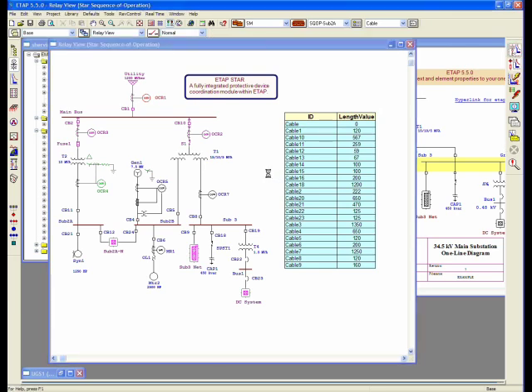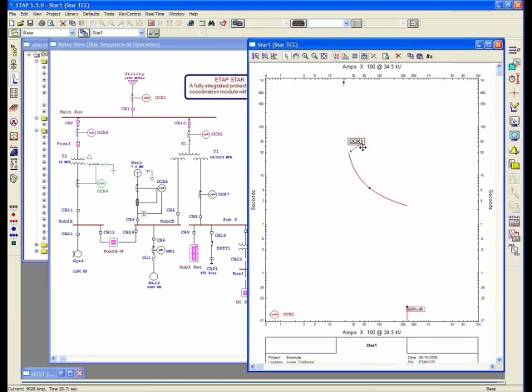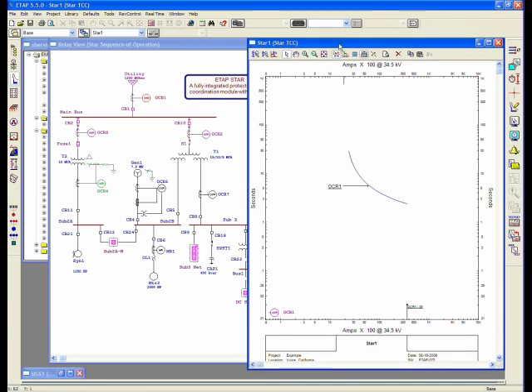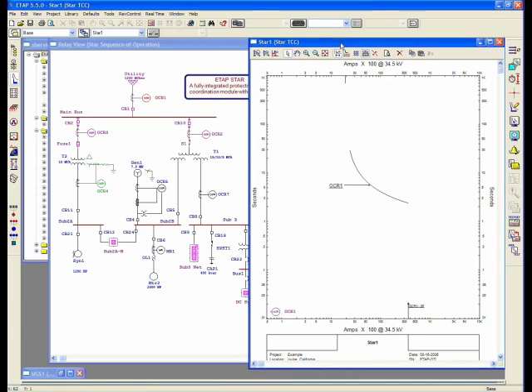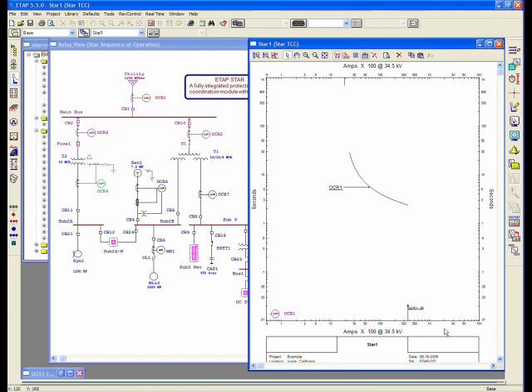What the program does, it brings that one-line element onto a TCC view and shows the label of the device, OCR1, and shows the curve for that device. This is created in what we call the star view, which is essentially a time-current characteristic curve of the device onto a presentation, which includes the seconds and current axis. There's a legend down here that you can modify as well.